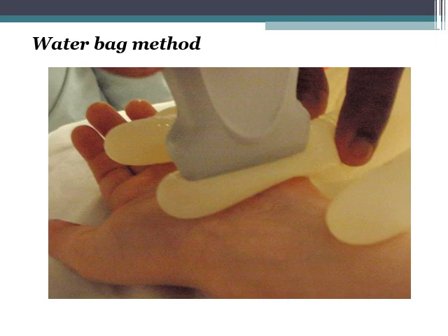The another method is water bag method. Here water is filled in a plastic or rubber bag. The water should be degassed and warm, and the bag is sealed. Then we can apply gel over the ultrasound head and over the treatment area, and then firm pressure should be applied from the head to the bag, and through this way the ultrasonic energy can pass from the water to the tissue, right?